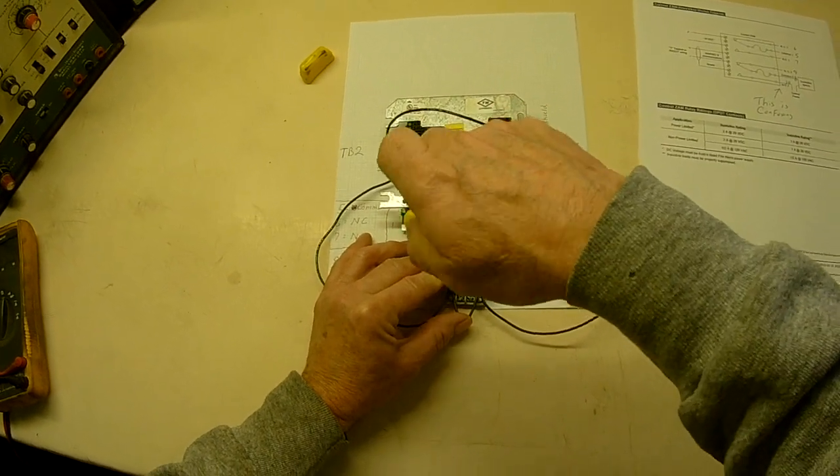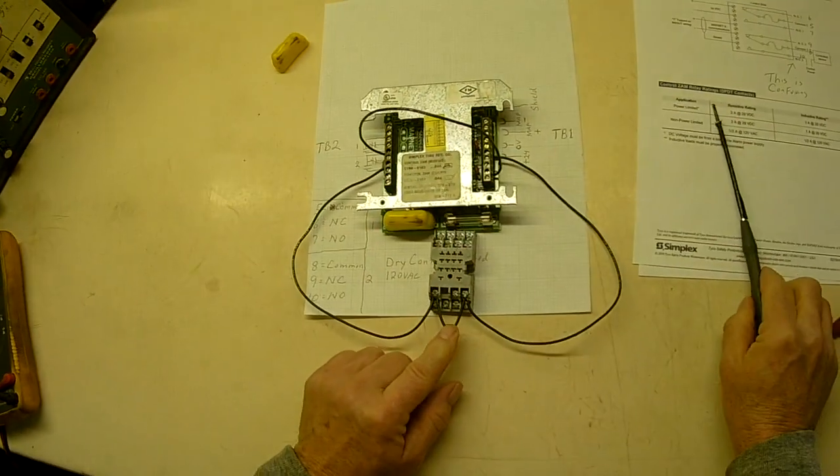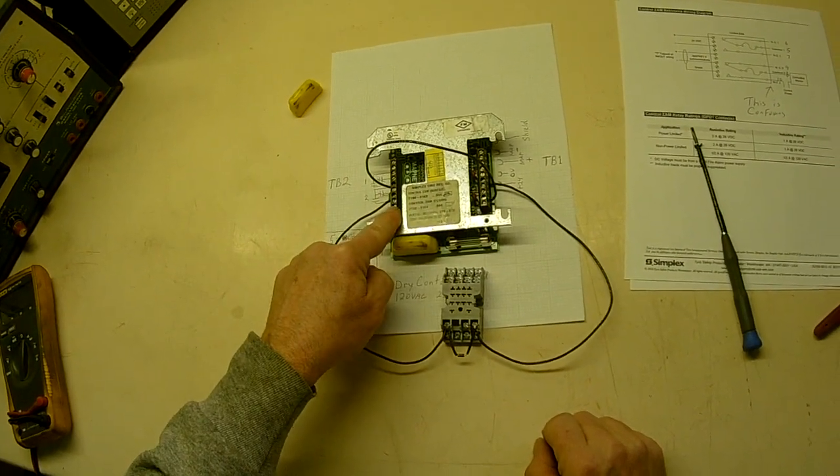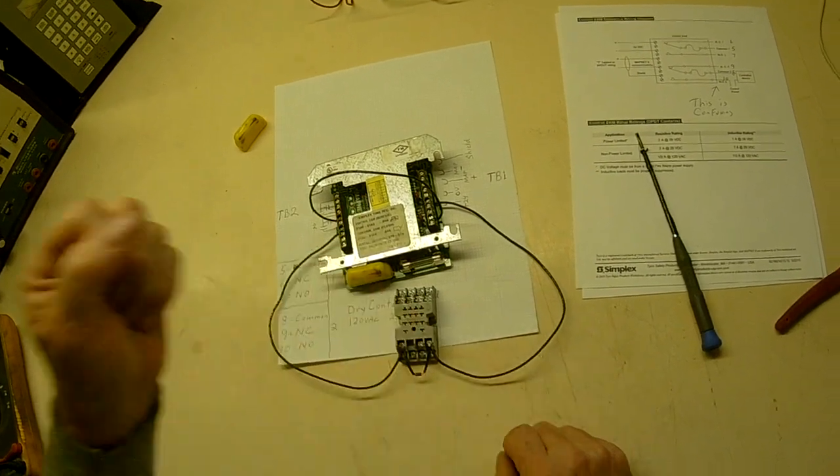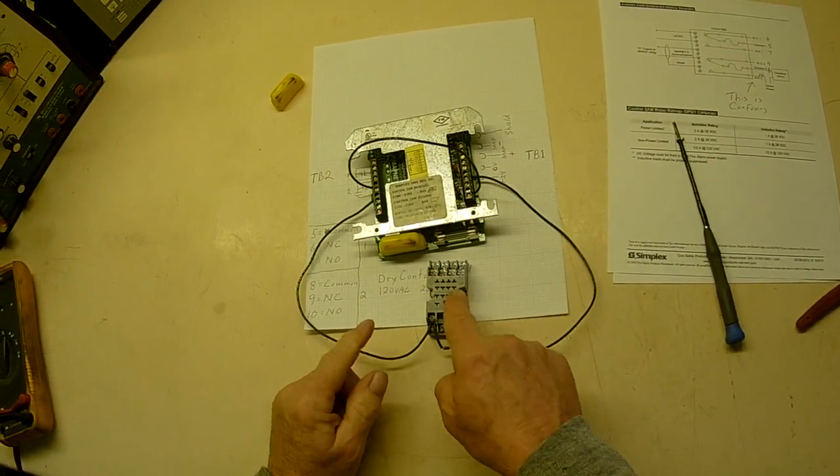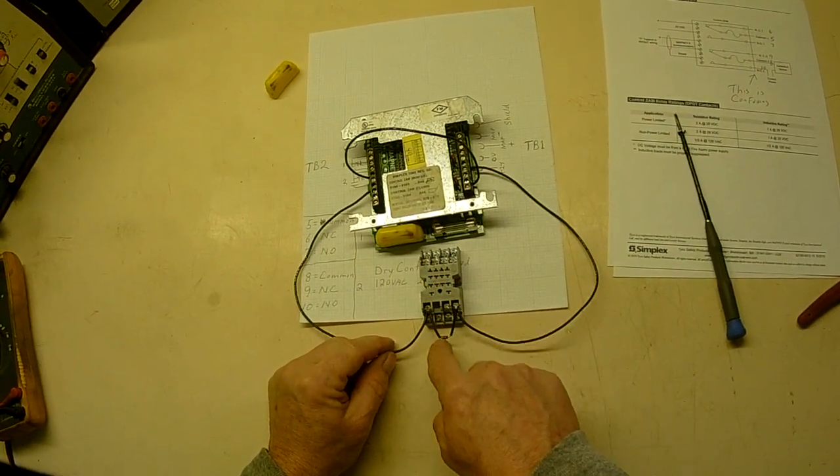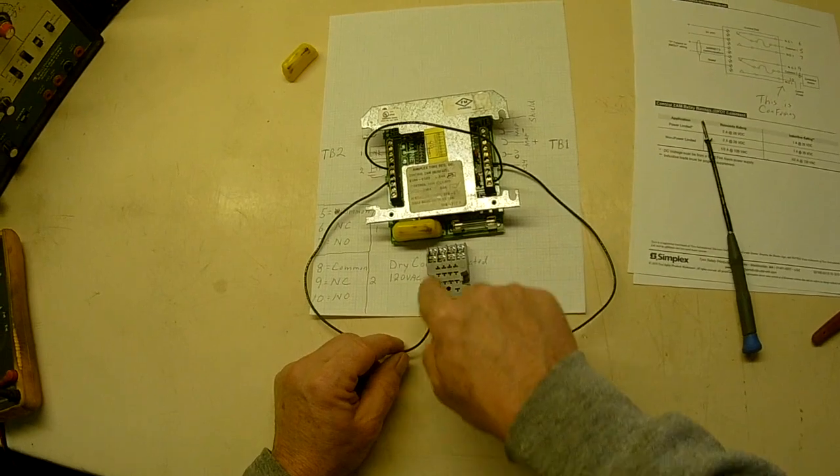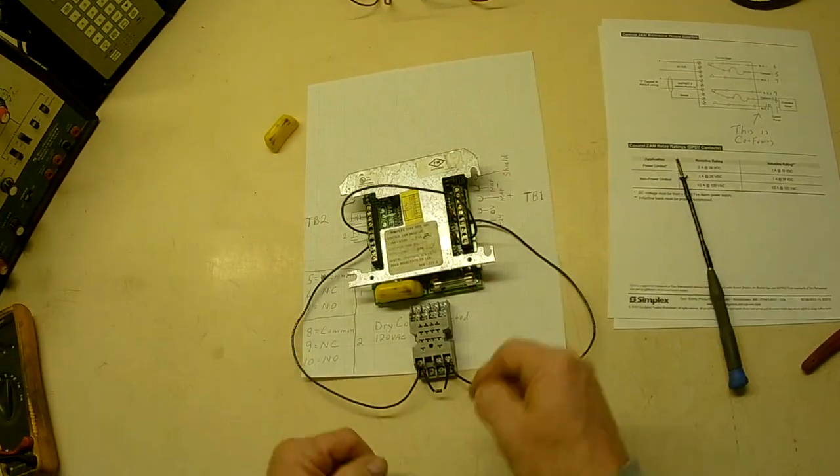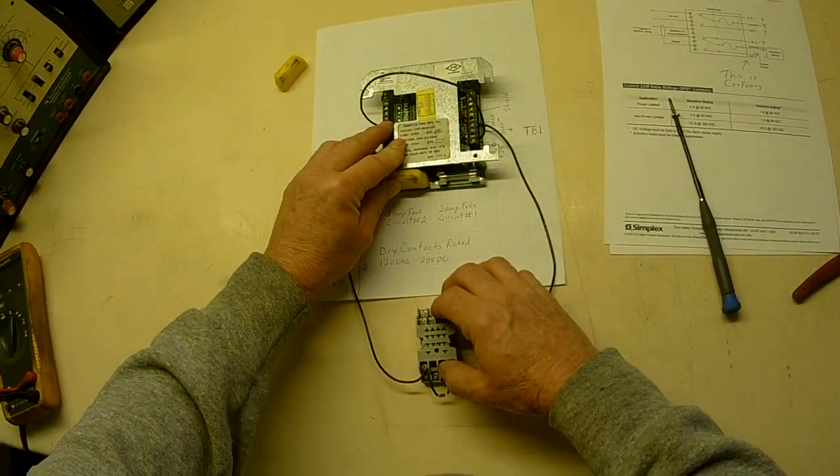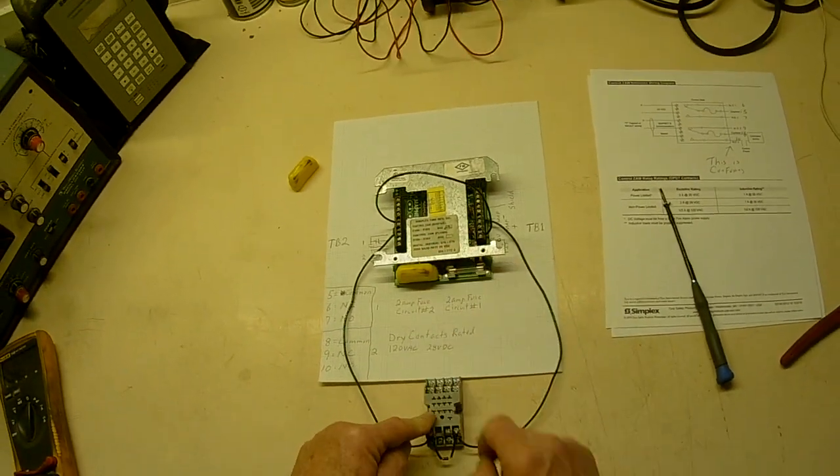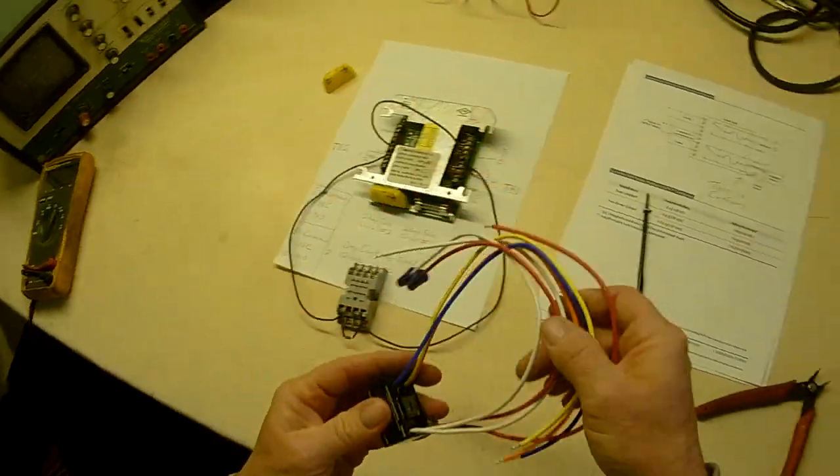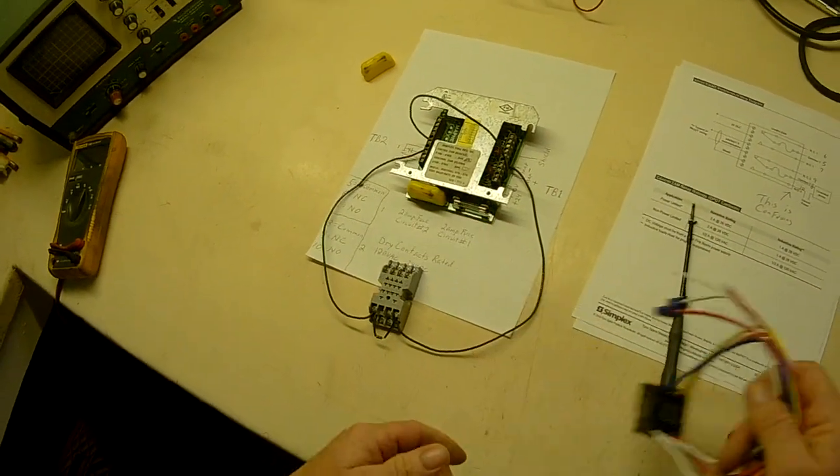Now why are we doing this? Why are we putting this diode in reverse polarity on the circuit? The reason for doing that is when this relay drops out, when it turns off, the voltage is released from this coil. This coil collapses and creates a spike of current. What it will do is it will come around through this diode. And it will neutralize itself. It will satisfy itself right there. That spike will happen right there and it won't go into that. So that's called a suppression diode. That's a little trick we learned to control things. The further away this is from there, that's fine. These PAM relays, you got it made. You know, it's already built into this thing. You know, they have one already built in, so we don't have to worry about that.